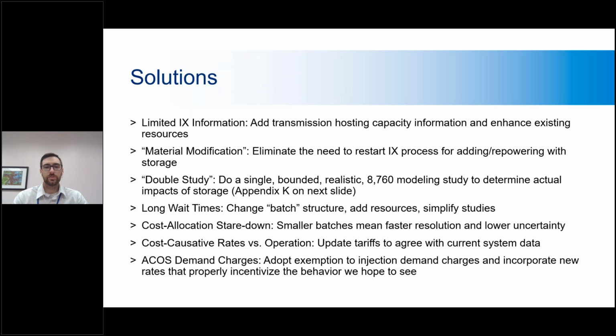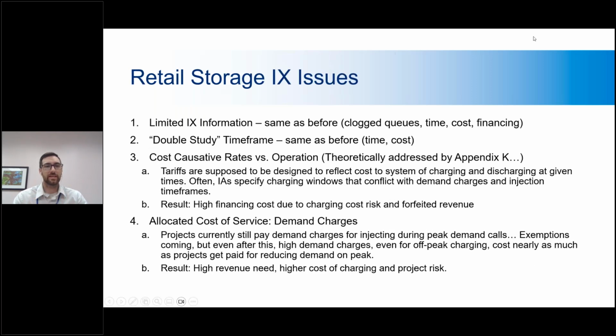Fourth, for retail storage, sorry, can we go back one slide? My mistake. The last point for retail storage is that we still have energy storage in New York State being charged demand charges for injecting power at peak times. This is a historical anomaly based on the fact that storage has historically been designated a standby energy resource, going back to the 1970s, when large industrials used DERs at their sites to mitigate utility rate charges. It doesn't really fit, but this is the rate structure our Public Service Commission has said storage should be on.